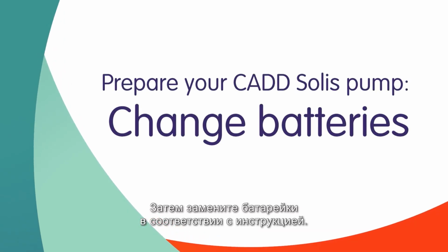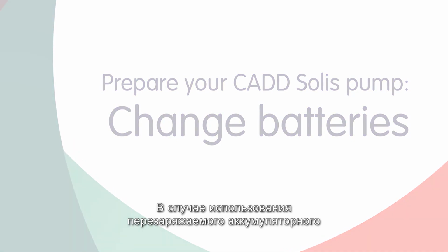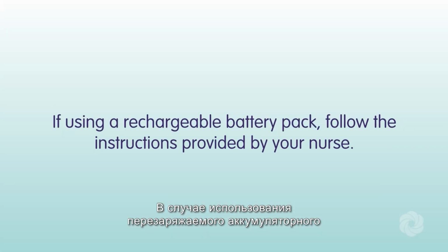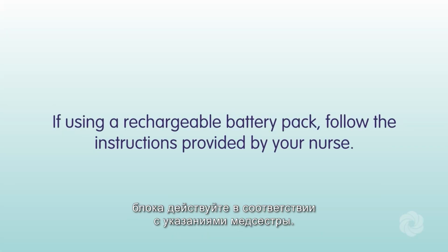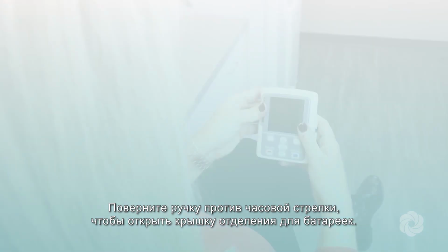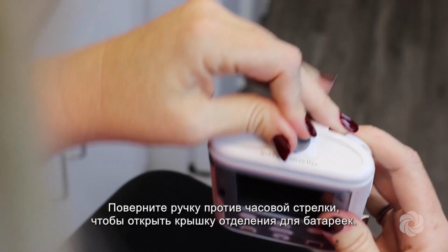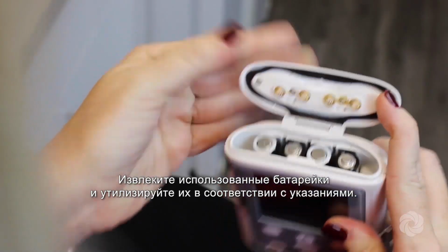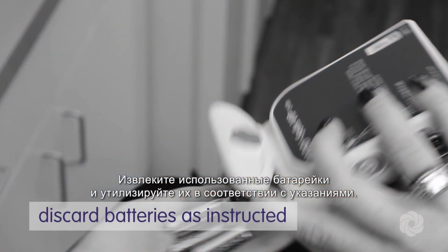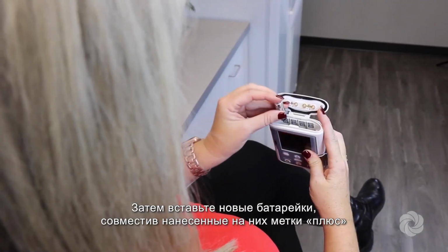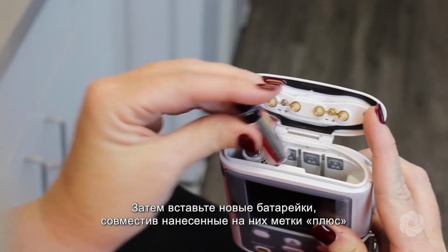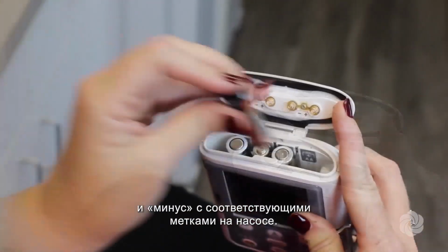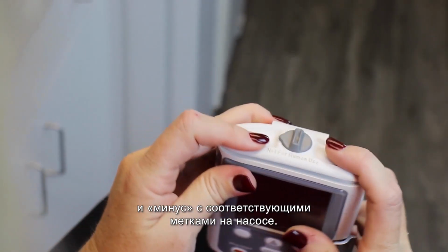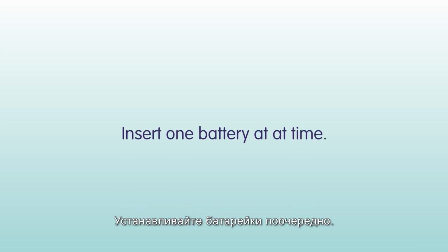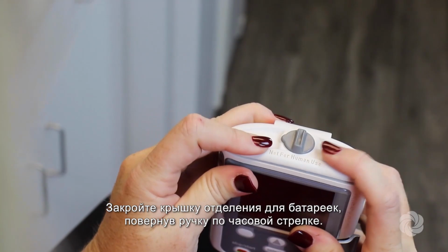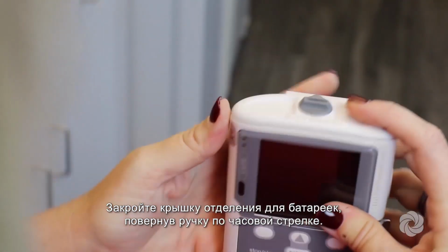Next, change the batteries as directed. If using a rechargeable battery pack, follow the instructions provided by your nurse. Turn the knob counterclockwise to open the door. Remove the used batteries and discard as instructed. Then, insert the new batteries matching the positive and negative markings on the batteries with the corresponding markings on the pump. Insert one battery at a time. Close the battery door by turning the knob clockwise to lock.